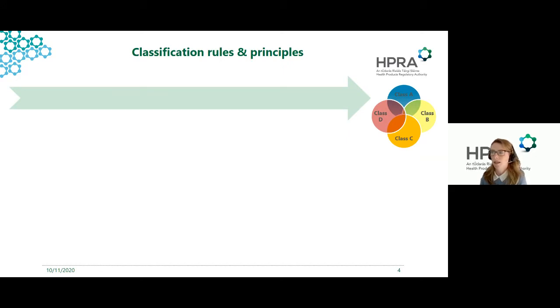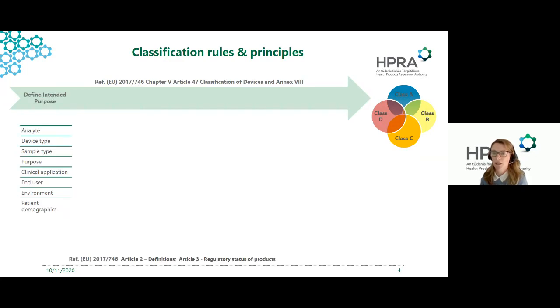Looking at the classification rules and the principles around classification: application of the classification rules is governed by the intended purpose of the device. It is very important, firstly, to define the intended purpose, taking into account all of the aspects of the device - what's being tested, what is the particular sample type to use, what is the clinical application, who is the end user of the device, what environment will the device be used in, and who is the patient. All of these need to be taken into account when defining the intended purpose, because application of the classification rules is very much governed by the intended purpose of the device.